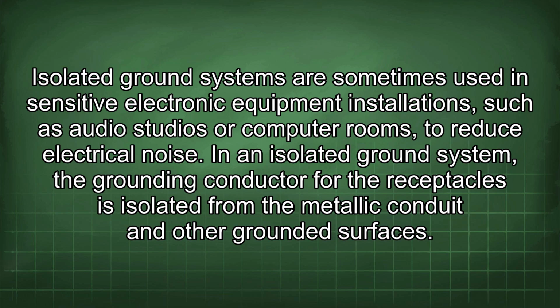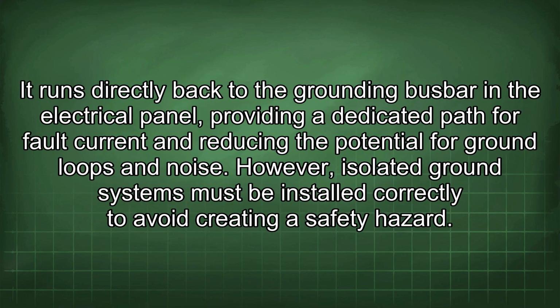Isolated ground systems are sometimes used in sensitive electronic equipment installations such as audio studios or computer rooms to reduce electrical noise. In an isolated ground system, the grounding conductor for the receptacles is isolated from the metallic conduit and other grounded surfaces. It runs directly back to the grounding busbar in the electrical panel, providing a dedicated path for fault current and reducing the potential for ground loops and noise. However, isolated ground systems must be installed correctly to avoid creating a safety hazard.